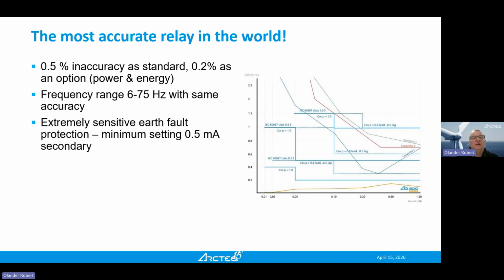Actually, one thing where we are also quite dedicated is the frequency range. We can set it to any frequency between 6 and 75. That's why we also have quite many devices on railways, which use 16 2/3 hertz frequency. So with our standard devices, we can make a railway protection device for Norway, Sweden, Germany, Switzerland, which have this different 16 hertz network.